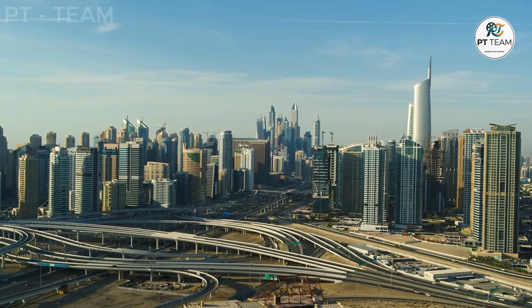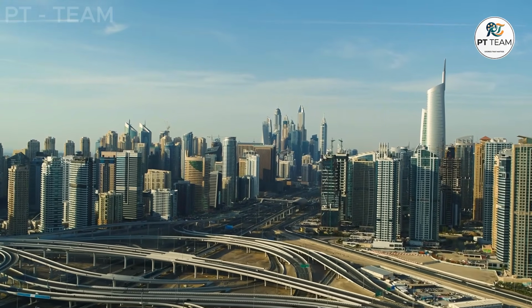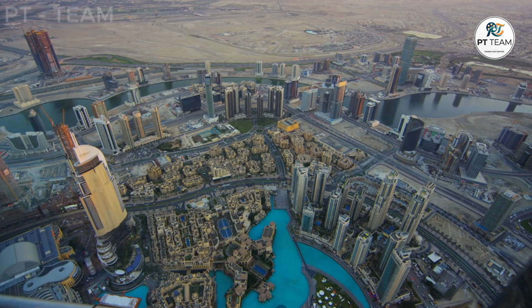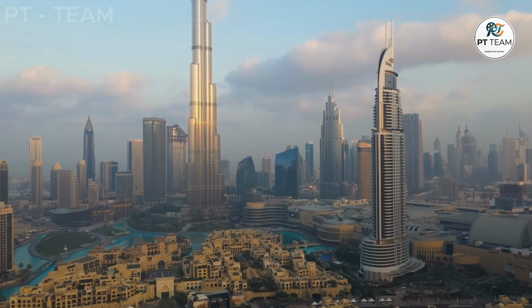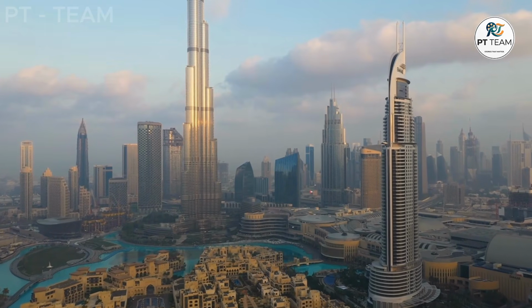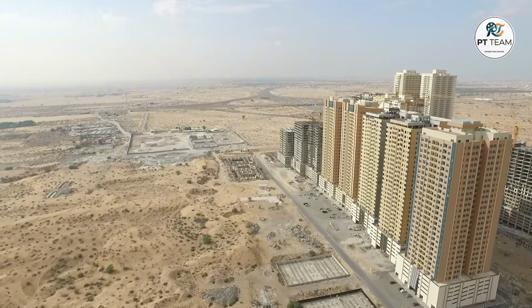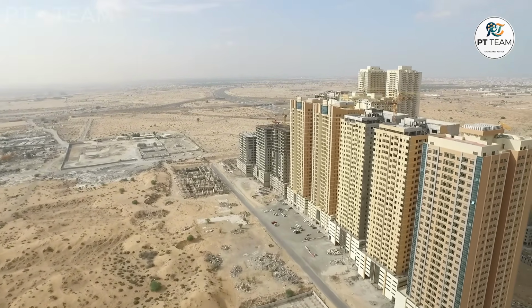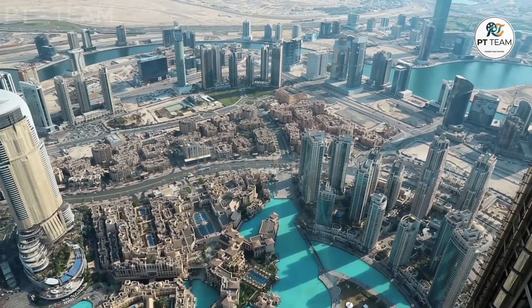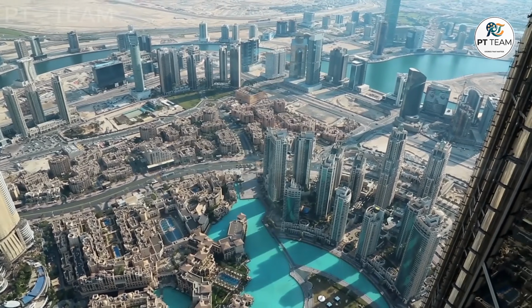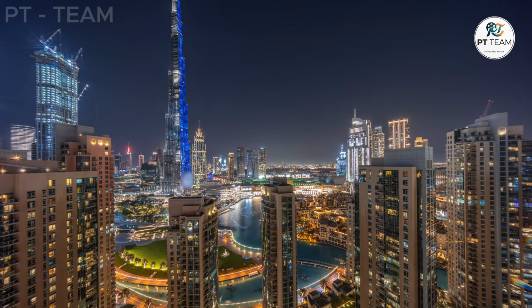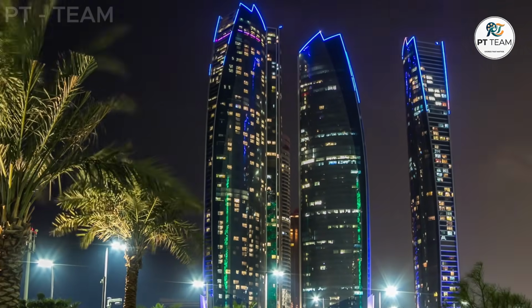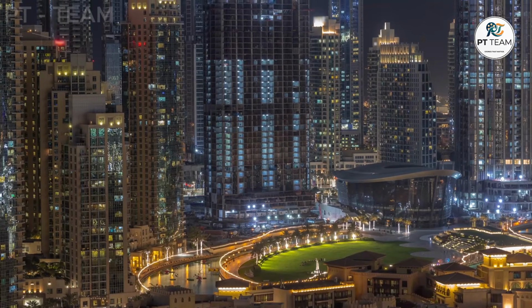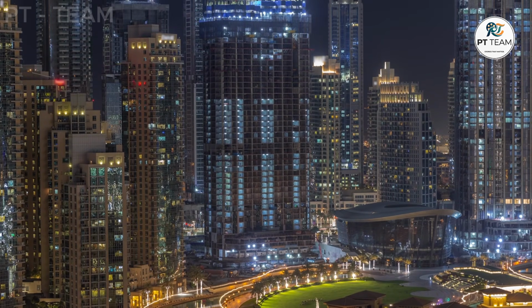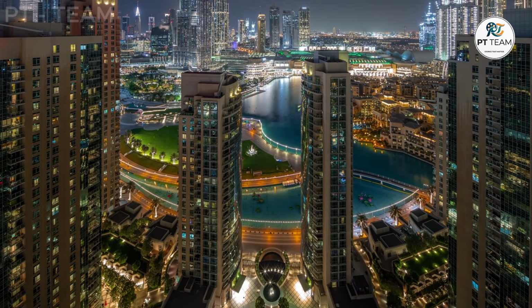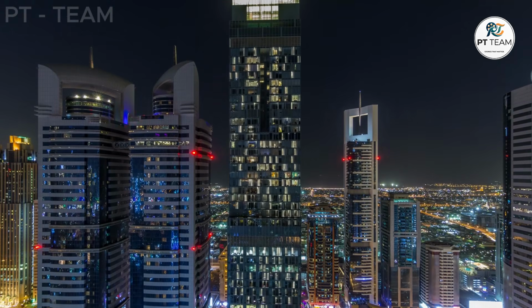Yet presenting Dubai as unaware of this structural problem would be equally misleading. The narrative that modern engineers simply forgot about the sun is entirely false. Dubai regulates building performance rigorously, and the mitigation strategies currently deployed across the city are highly sophisticated. High-performance glazing works exactly as it was designed to work, deflecting immense amounts of radiation. District cooling can dramatically improve urban energy efficiency compared to relying on thousands of decentralized air conditioning units. Intelligent building management controls successfully reduce unnecessary cooling loads by tracking occupancy and adjusting airflow. Strategic architectural shading and better facade orientation demonstrably reduce the worst of the direct solar exposure. Engineers actively model, calculate, and manage solar heat gain long before the first concrete foundation is ever poured.